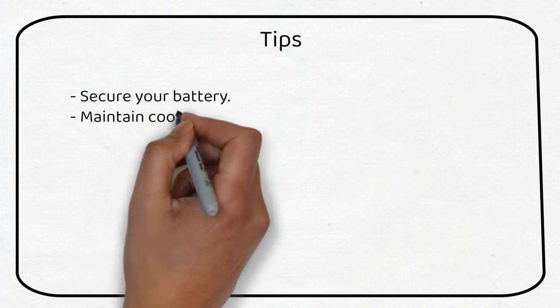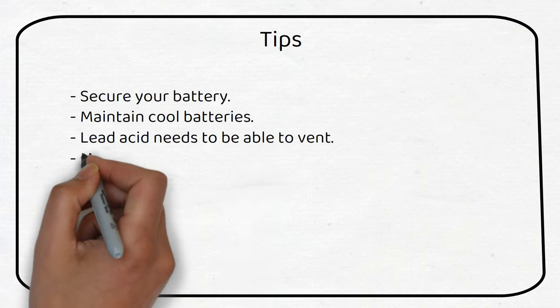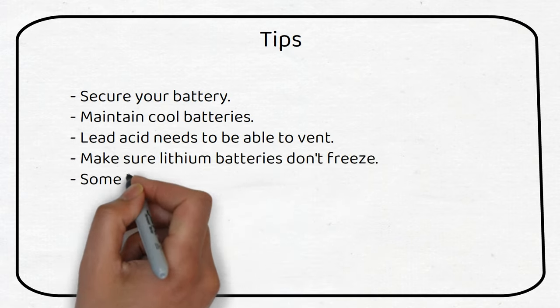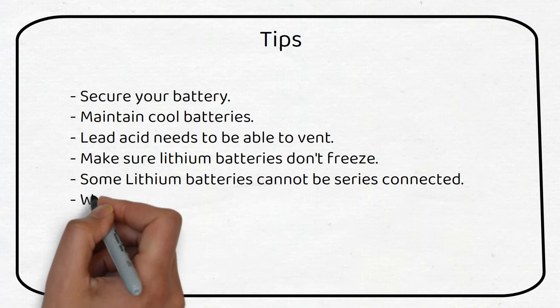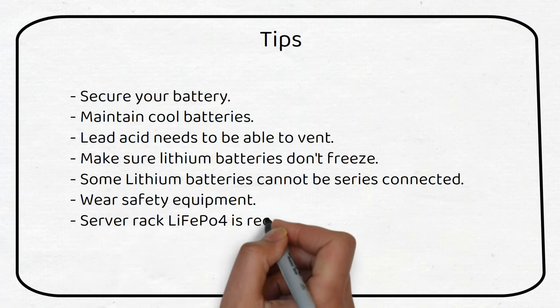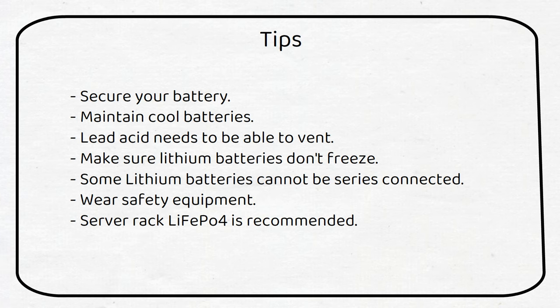If your battery bank is subject to vibrations, make sure it's mounted securely. Maintain cool battery temperatures to increase lifespan. Make sure lead acid batteries can be ventilated, even when it's sealed. Do not charge lithium batteries below freezing. It will damage the battery.